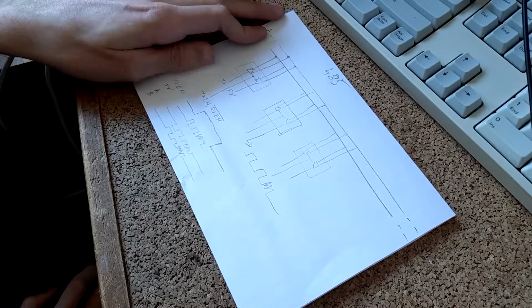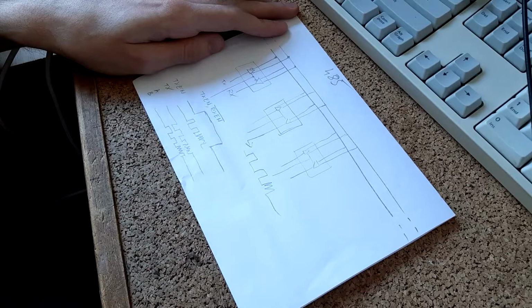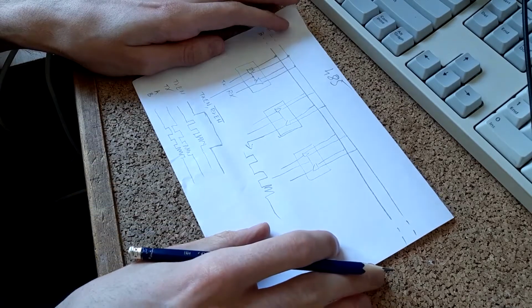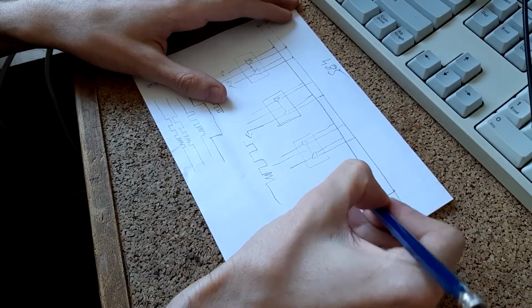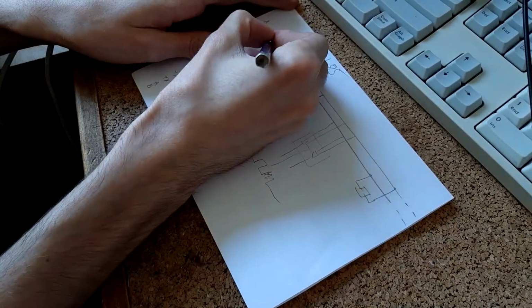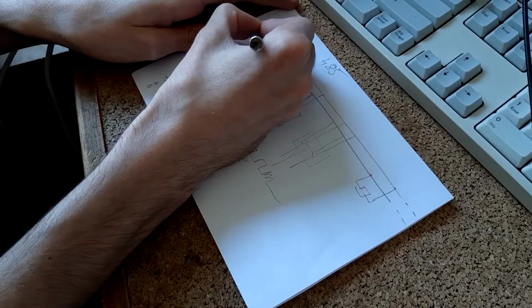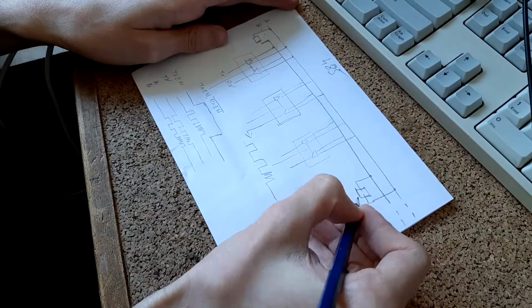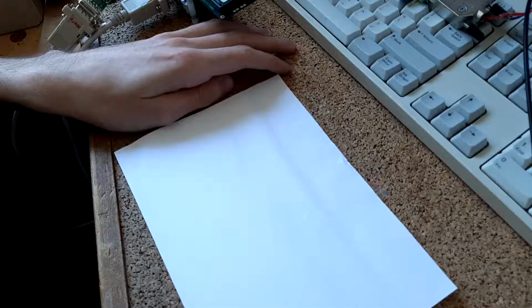And this way you send bytes over 485. So when you're done transmitting, you pull the TX enable line low, and you start actually listening for the other device's data. What is also not drawn here is that you need bus terminators on both ends of the line, and that is to prevent reflections, which mostly has an effect on longer buses and higher speeds, but it's a good measure to add them anyway.